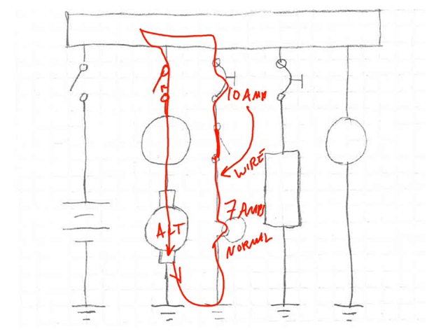You'll notice at 9.9 amps, will 9.9 amps pop this circuit breaker in theory? No. But what about the light bulb? If it's designed for 7 amps, but you push 9.9 amps through it, what's going to happen to the light bulb? Will it be brighter or dimmer than normal? It'll be brighter if you push more electrons through it. How long will that light bulb last compared to putting 7 amps through it? It won't last as long. You see what I mean? The circuit breaker is not there to protect the component. It's not there to protect the device. The circuit breaker is there to protect the wires from getting so hot that they will cause an electrical fire.